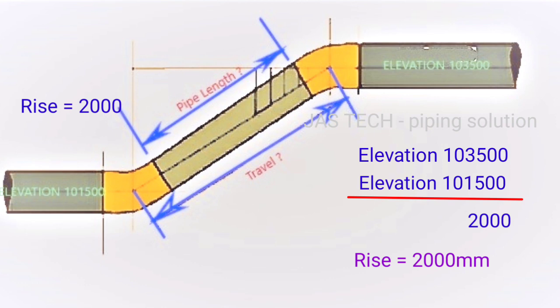So our elevation: elevation of the top pipe is 103500, elevation of the bottom pipe is 101500. So you minus from top pipe to bottom pipe. The result will be 2000. That 2000 is the rise side measurement.